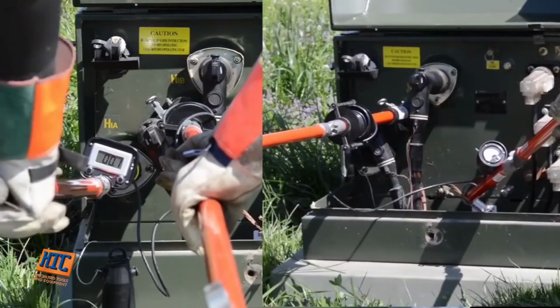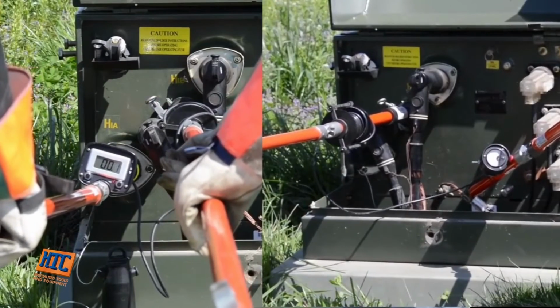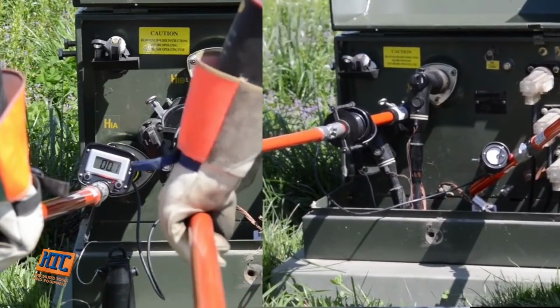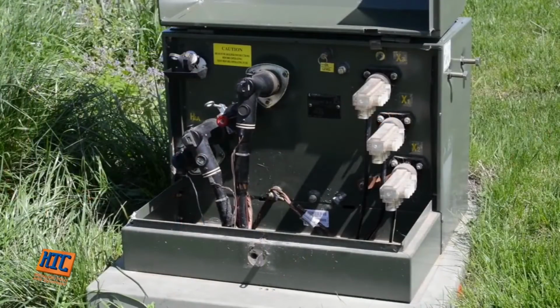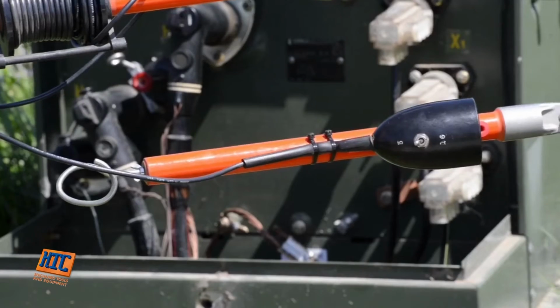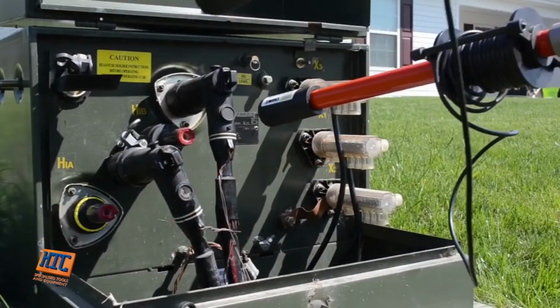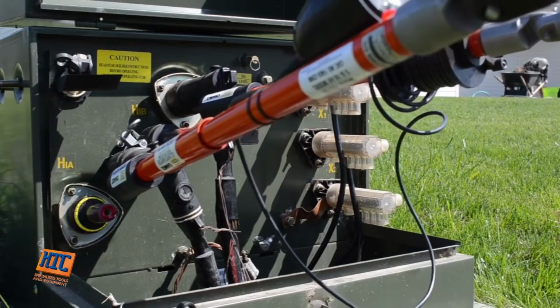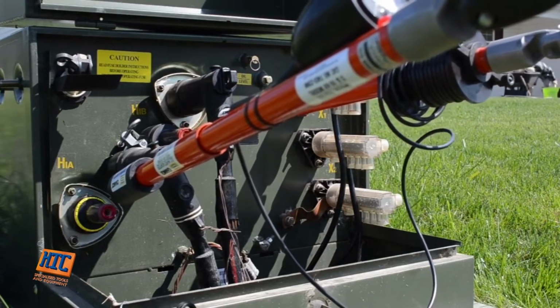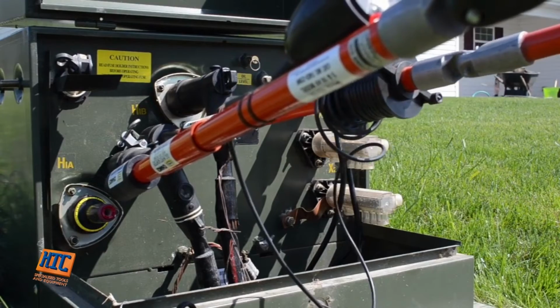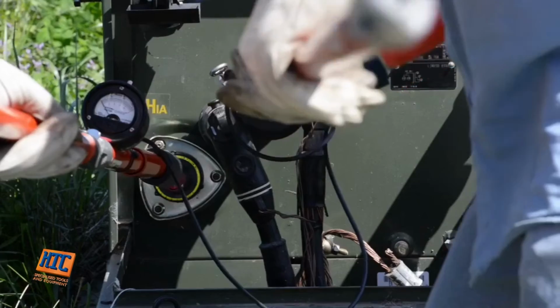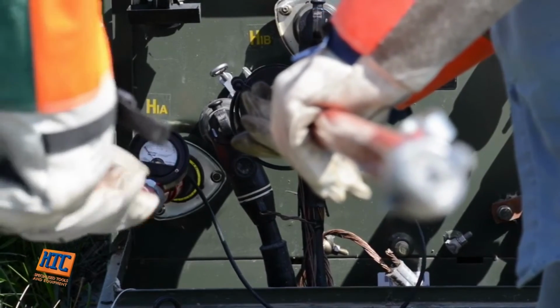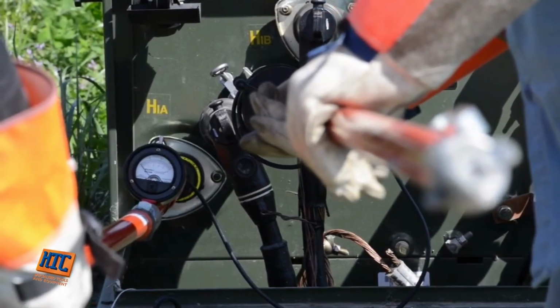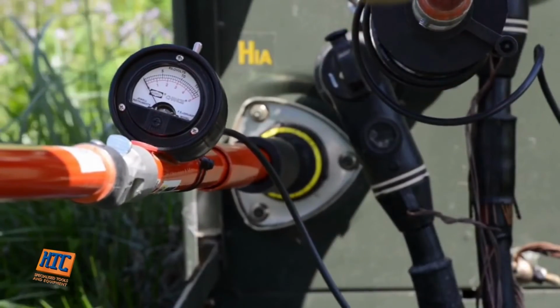Both types of phasing testers can also be used for high-pot proof testing and underground cable repair prior to putting it back in service. The cable has been isolated on the other end. Here again, notice that the cable's 200 amp load break elbow already has been pulled and parked on a feed-through, all with hot sticks. With a DC high-pot adapter on the meter stick and a bushing adapter on the reel stick, insert the meter probe into the energized bushing and the other probe into the feed-through.